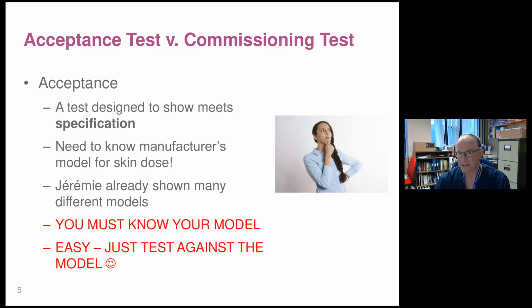So if you're going to do an acceptance test on a skin dose mapping or a dose mapping product, you need to know the manufacturer's model. Otherwise, you don't know if it's doing what it says it should be doing. It's not about is it right or wrong in the real world. It's does it do what it says it's going to do?